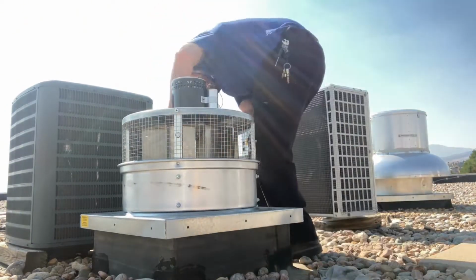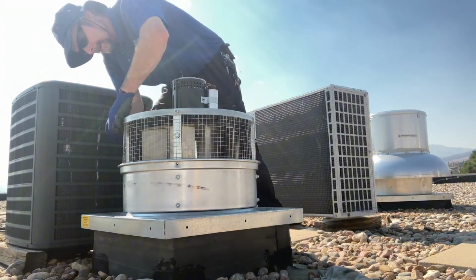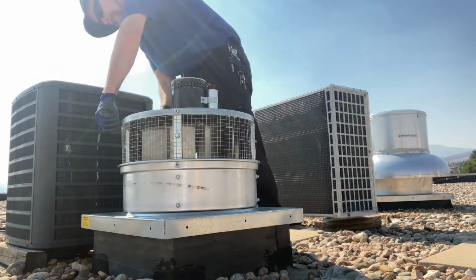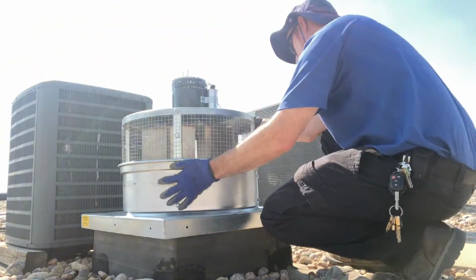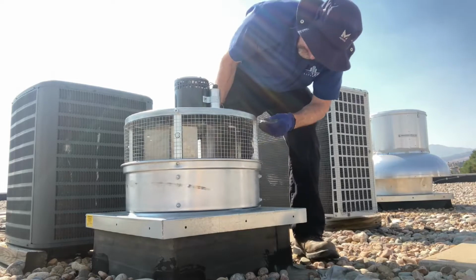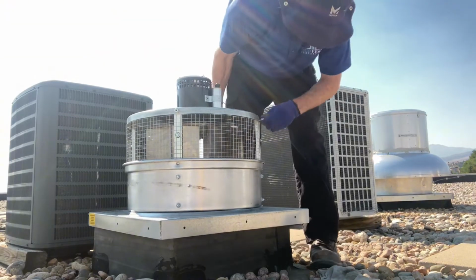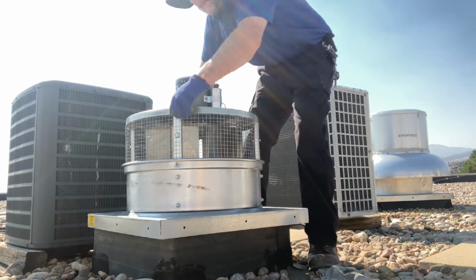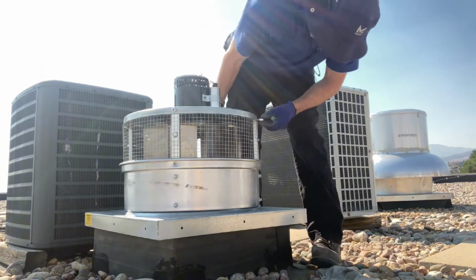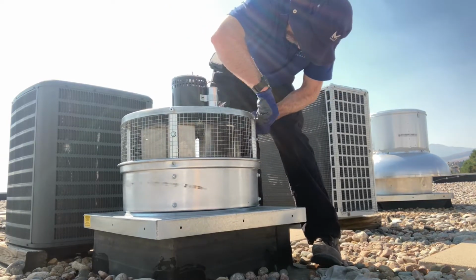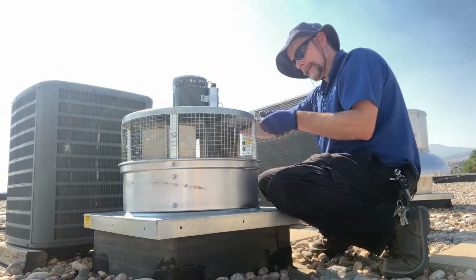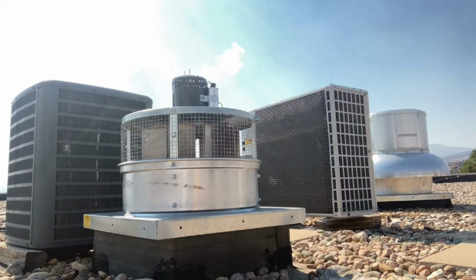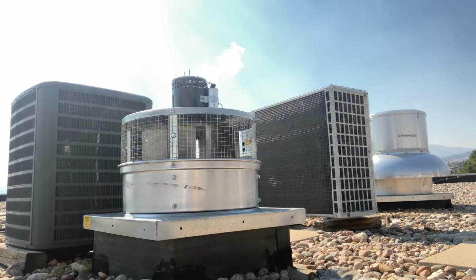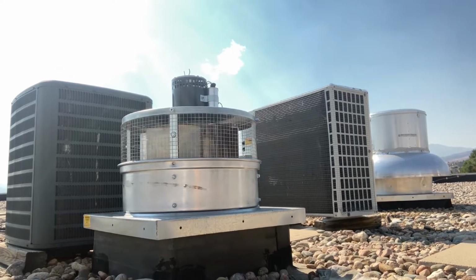Something important to note, when you're replacing an exhaust fan on a roof like this, you want to make sure the new exhaust fan specs match the specs of the old exhaust fan and the measurements match. So what's the length and width of your roof curb? The voltage, is it single phase, three phase, RPM, CFM rating, etc.